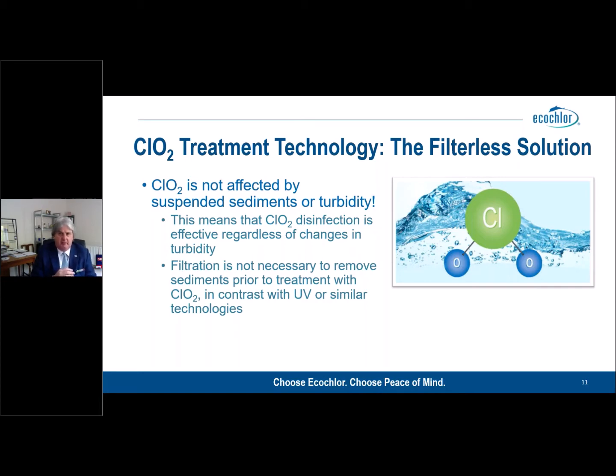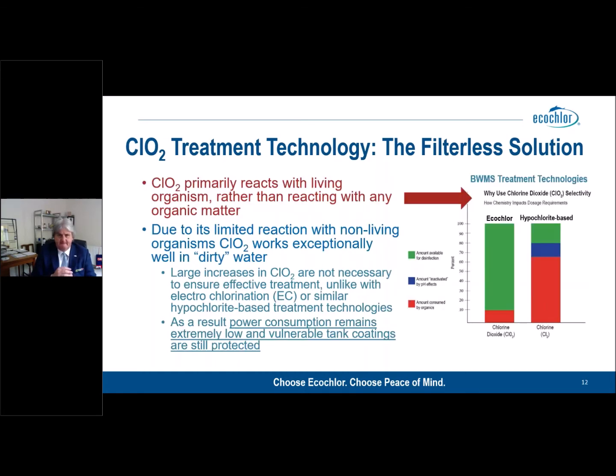But perhaps what's less well known is why you might need a filter unit on an electrochlorination or hypochlorite-based system. If I could have the next slide, please. The reason why you may very well require a filter unit for reliable and efficacious operation on a hypochlorite or electrochlorination-based system, as compared to a chlorine dioxide-based system, is simply down to physics, chemistry and biology. Essentially, the two different methods of disinfection work in fundamentally different ways.